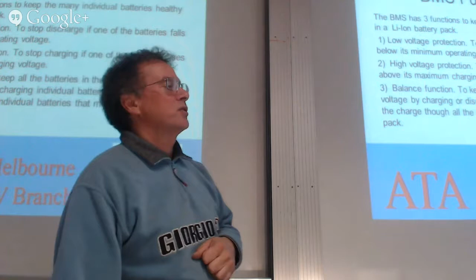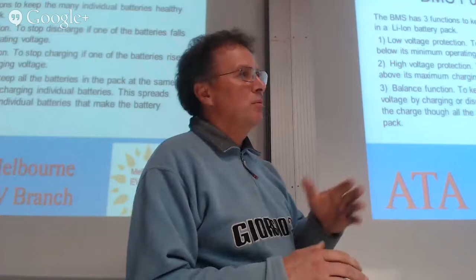High voltage protection protects the battery when it's being charged, because some individual batteries in the pack might charge faster than others and their voltage rise is too high. So the BMS also has to give protection when charging, so individual batteries don't overcharge. The last function of the BMS is the balance function, which keeps all the battery packs at the same voltage by distributing the charge throughout the entire pack so all the batteries have a similar rate of charge.